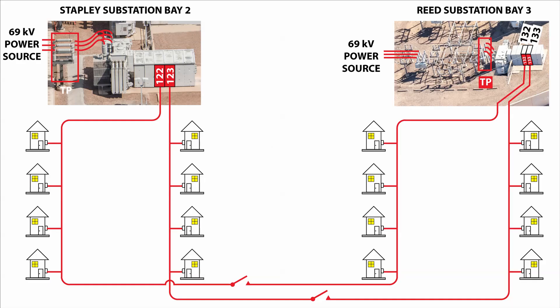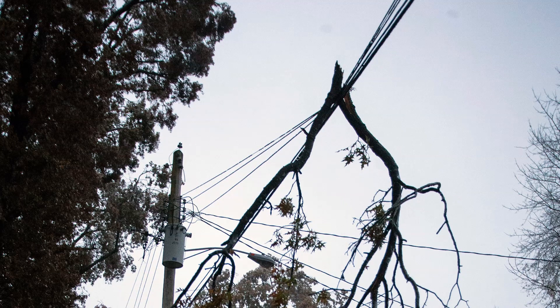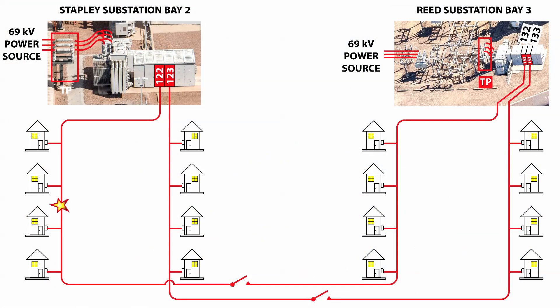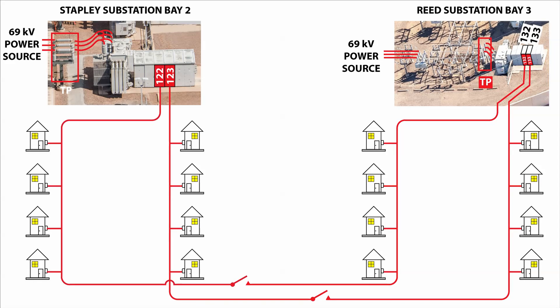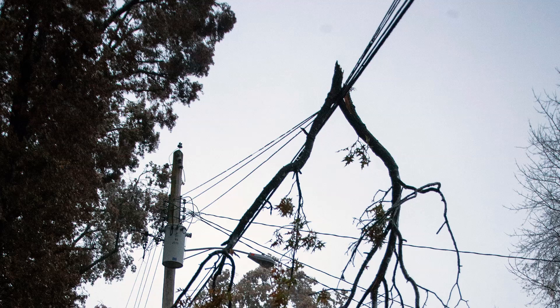The first scenario we will discuss is a fault which occurs on the circuit fed by Stapley circuit breaker 122. A tree branch breaks in a storm and falls onto an overhead line. At first when the fault occurs, a relay senses the fault and the circuit breaker in the 122 cabinet opens momentarily and then automatically recloses. The idea of reclosing is that some faults are temporary — for example, a tree branch, after contacting the power line, may fall to the ground clearing the fault.